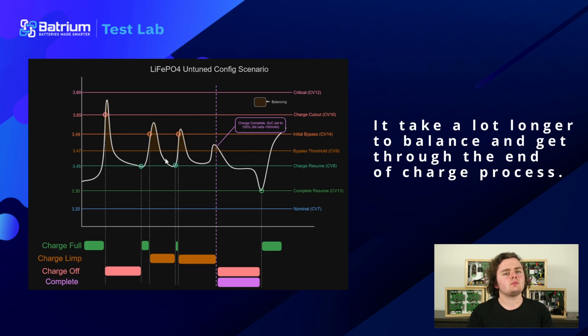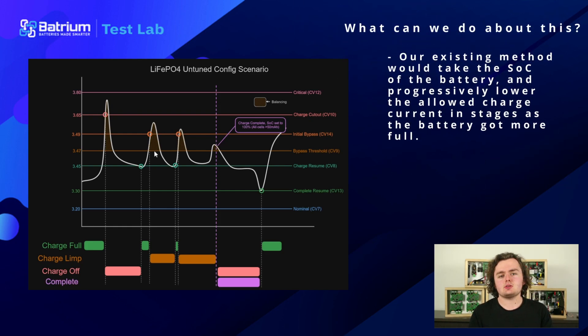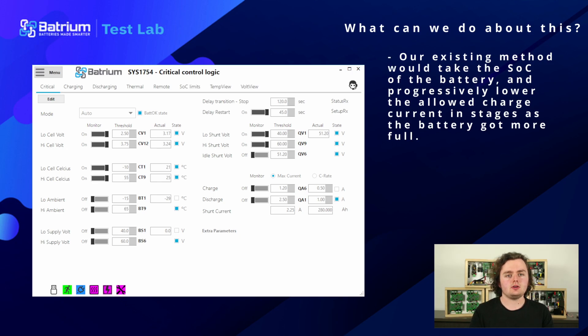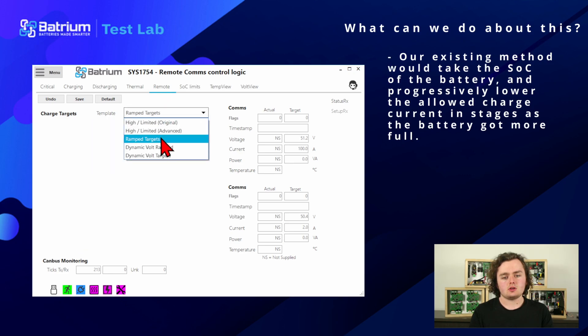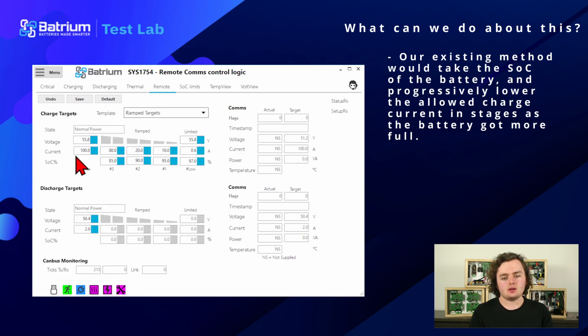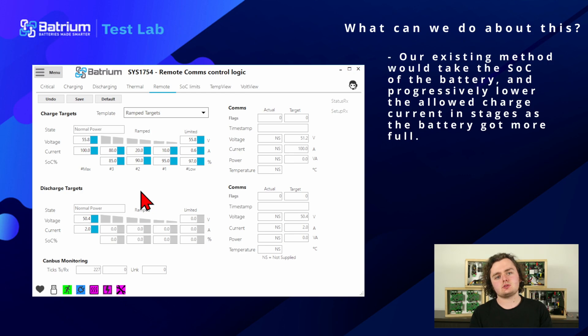So what can we do about this? Our existing method would take the state of charge of the battery and progressively lower the allowed charge current in stages as the battery got full. That's over here in remote and it's called ramp targets. It sets progressively smaller values as the state of charge gets closer and closer to full. It's one way of doing it, but it's a bit complicated, doesn't work for all systems, and also relies on charts.